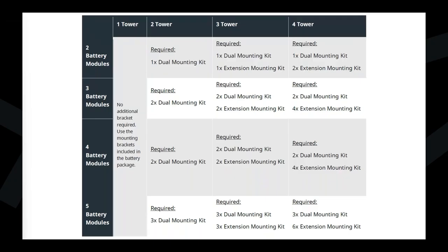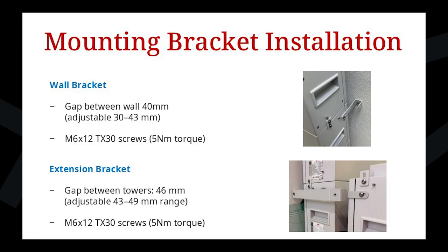All right, so in terms of the mounting bracket installation, when installing the wall bracket, just note that the gap between the wall and the battery can be between 30 and 43 millimeters, okay? And you're going to use an M6 by 12 T30 screw at 5 Newton-meter torque to attach those brackets. Same with the extension brackets as well. And the gaps between each tower can be between 43 and 49 millimeters.